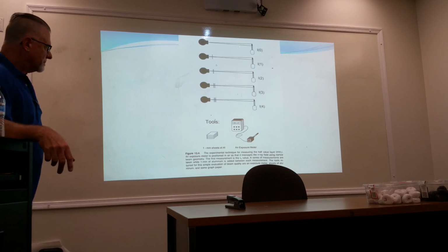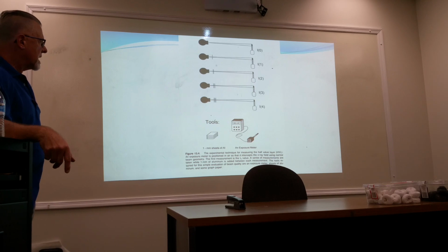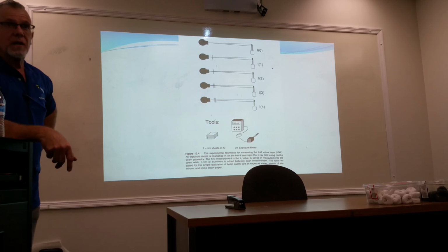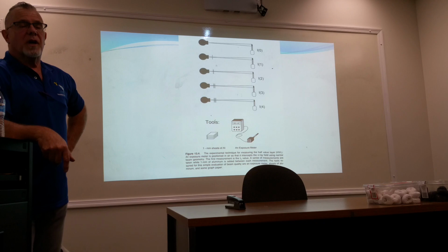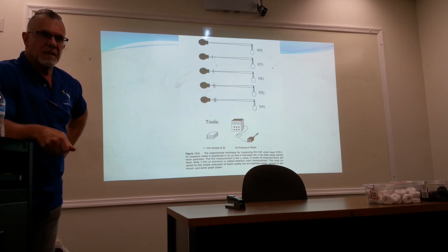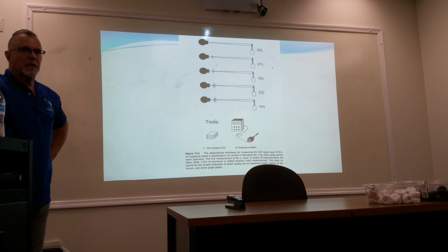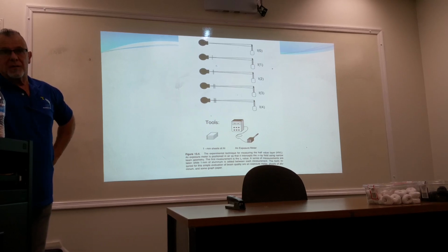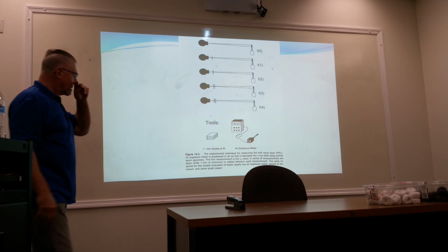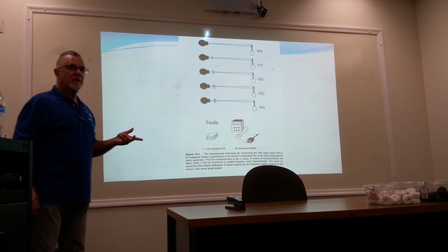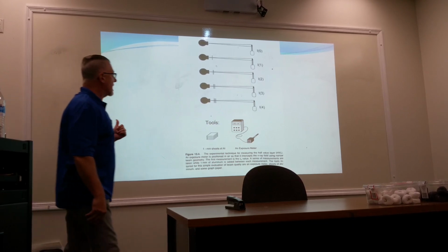Half value layer is something that is technically measured only at acceptance and if you change an X-ray tube or collimator, then half value layer under state regs has to be measured again.